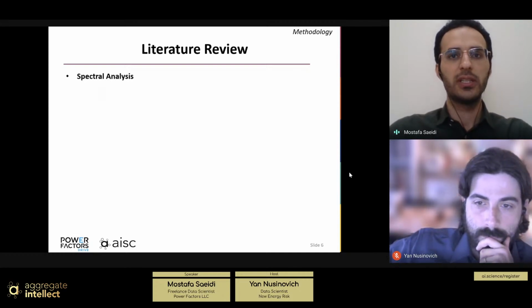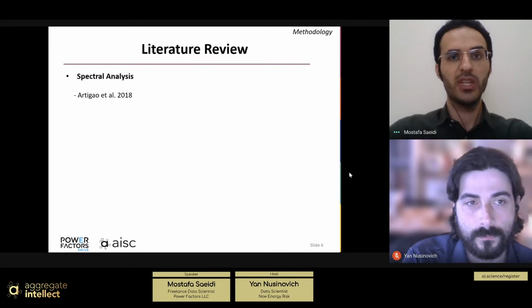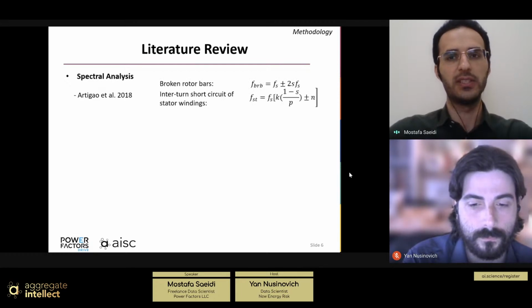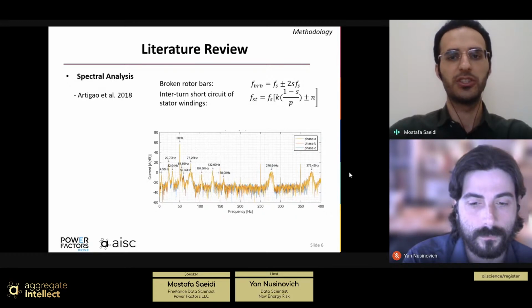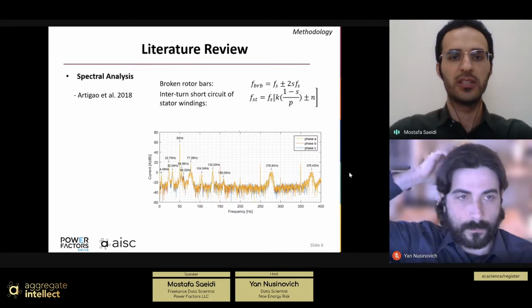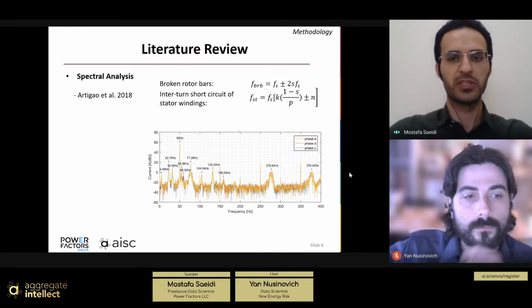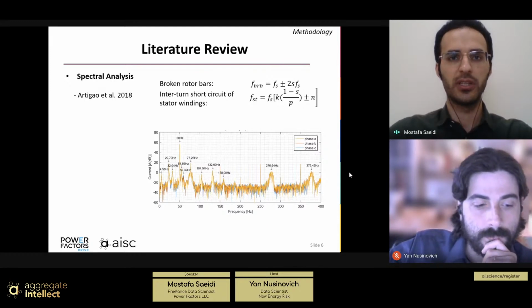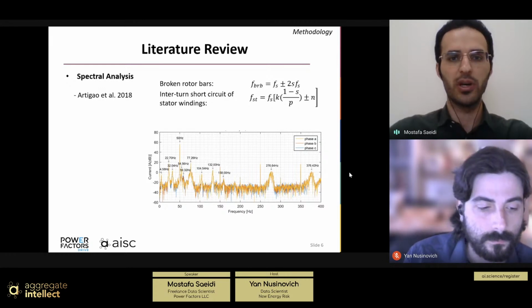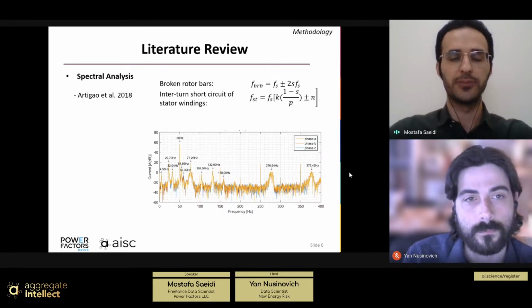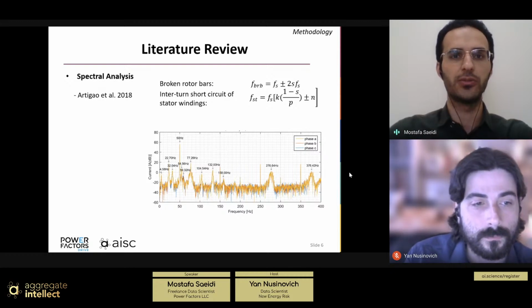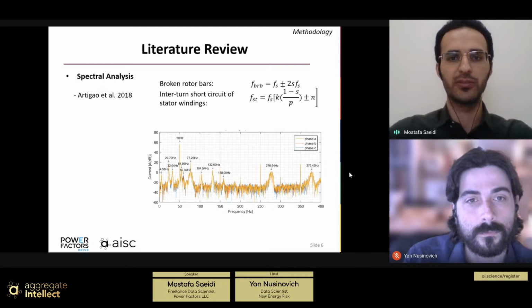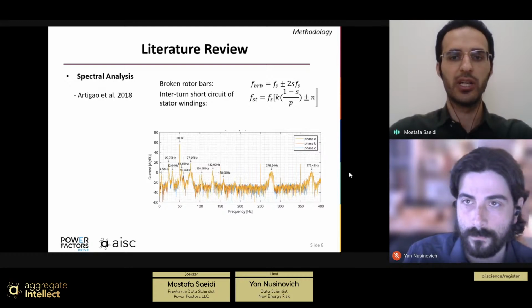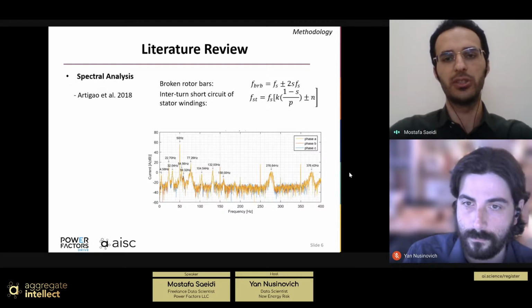The first method that was used for the anomaly detection was spectral analysis. In this paper, they suggested that we can extract the frequency spectrum for stator current of generator. When we draw this frequency spectrum, we can see that when there is a fault, for example, broken rotor bars, there would be a spike in some frequencies that shows that the problem is related to the broken rotor bars. In other words, each of the failures has its own signature in terms of the increasing frequency, and by extracting the frequency spectrum, we can detect what type of fault is in the system.